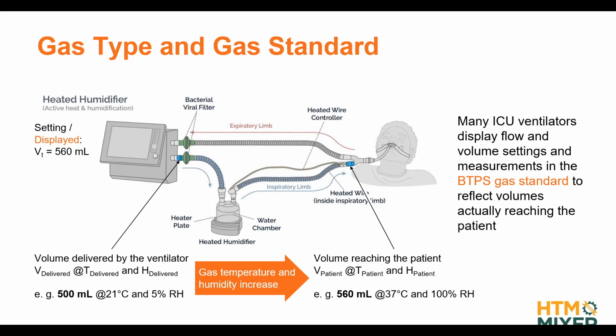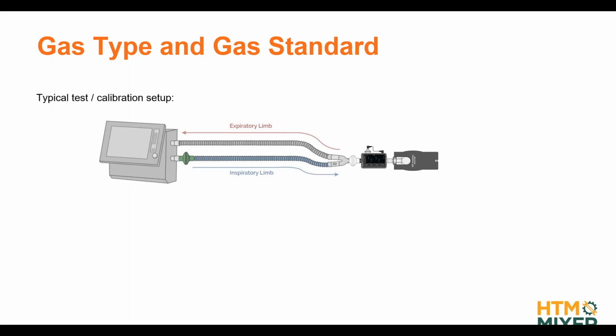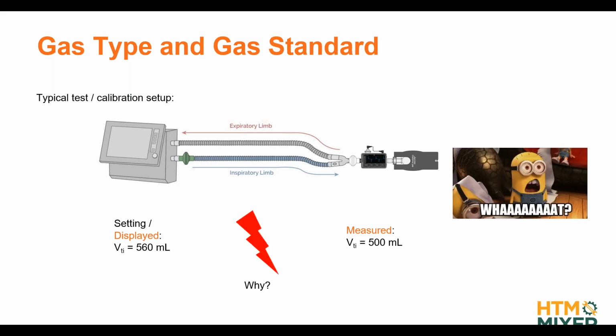All right, so what is the problem here? When we test such a ventilator with our gas flow analyzer, our setup typically looks like that, right? You just have a circuit system, then an analyzer, a test lung, and in such a situation it can easily happen that you set up a tidal volume of 560 milliliters on your ventilator, and then you measure with your analyzer, oh, just 500 milliliters. What's wrong here, right?